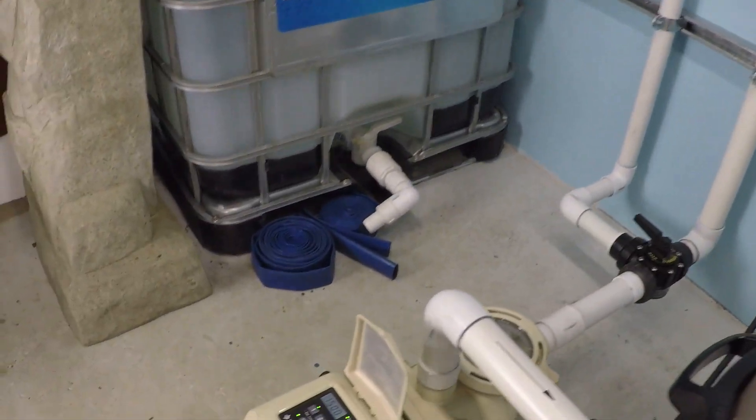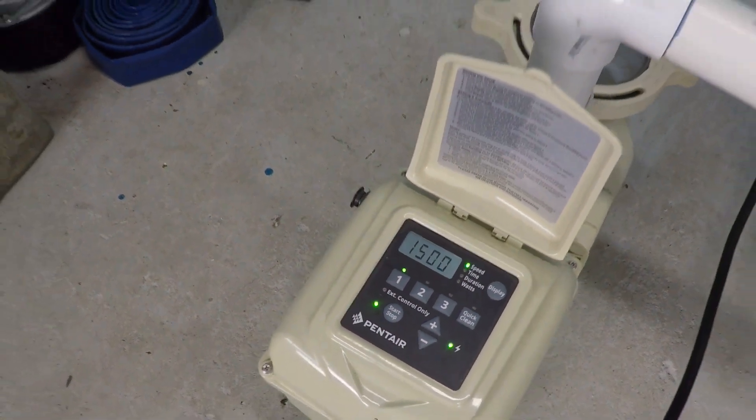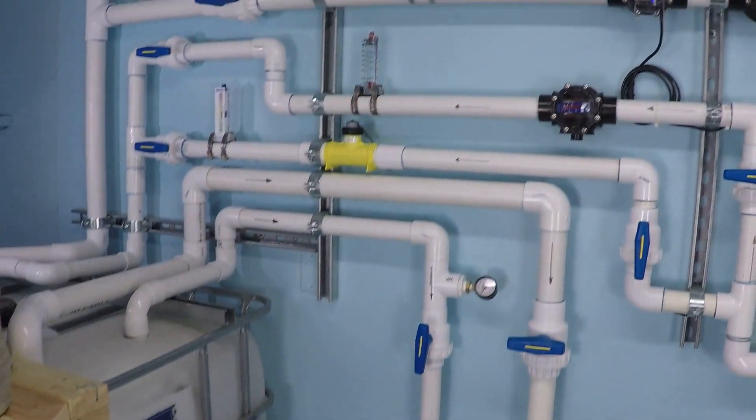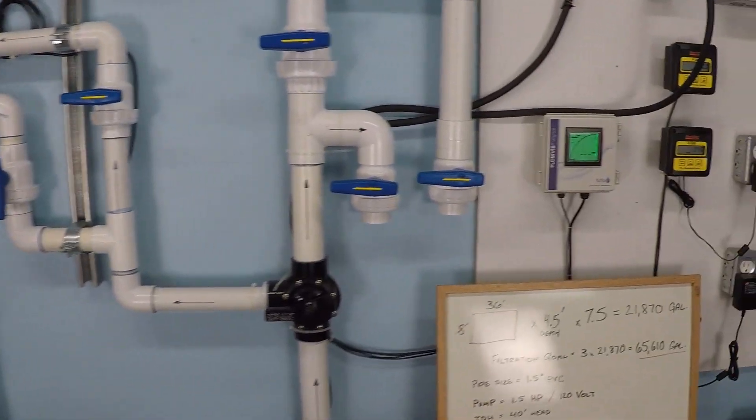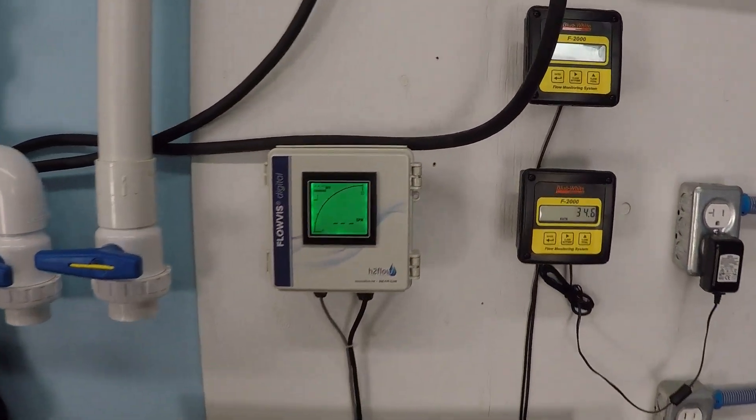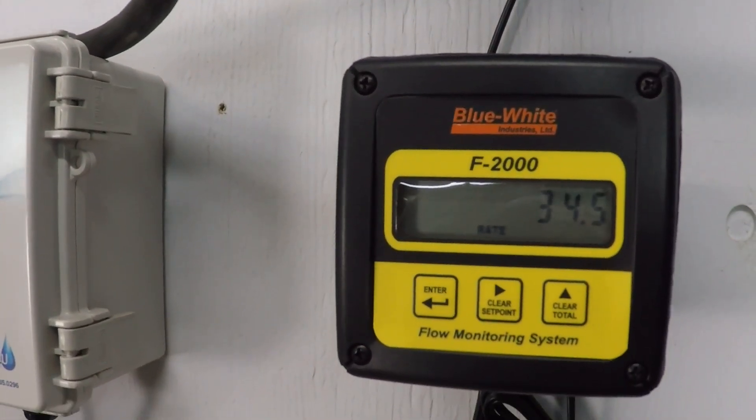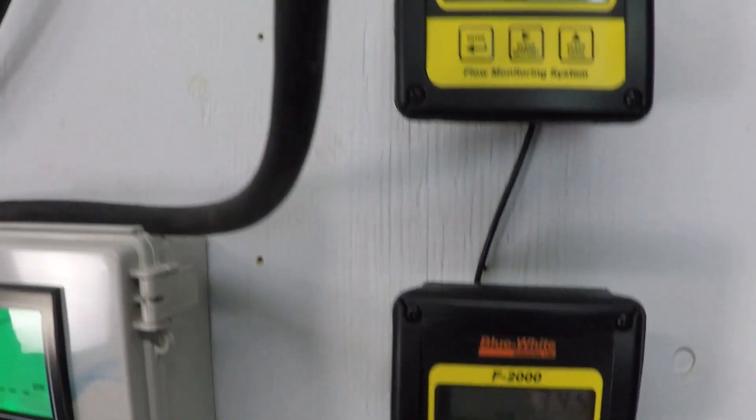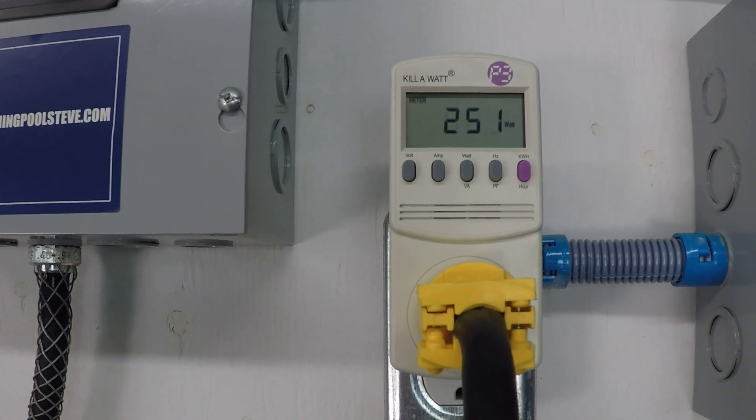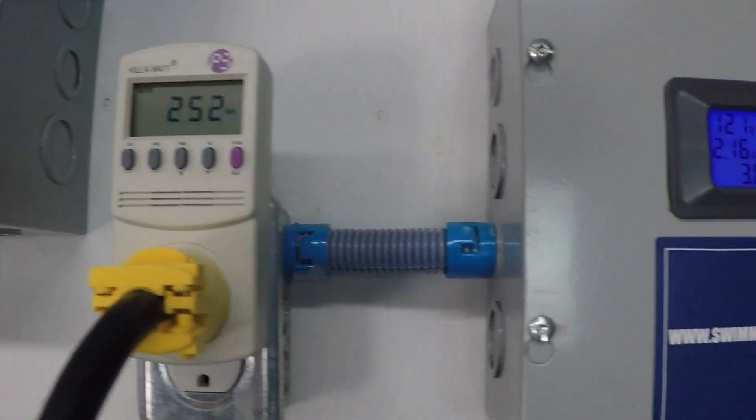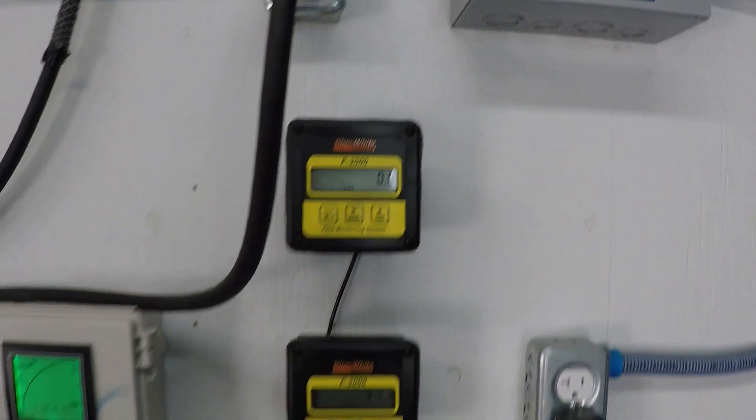So just to show you, running on this system right now we have a 1.5 horsepower variable speed pump running at 1500 RPM on a 1.5 inch system. We're monitoring through suction and return - just under 35 gallons per minute, just over 250 watts, 252 to 253 watts there.